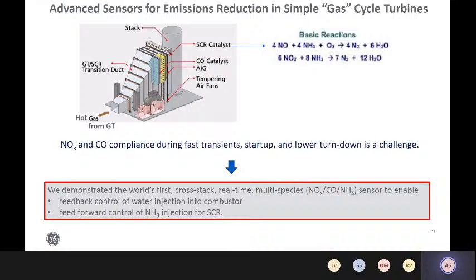So there is really a need for figuring out a way in which you can reduce startup emissions in places like California and other places where we have stringent emission requirements. What GE has done in order to reduce startup emissions in some of these simple cycle gas turbines is to inject water into the combustion chamber itself. What this does is it reduces the temperature and therefore it reduces the NOx.